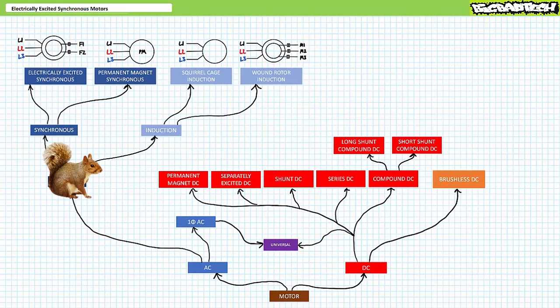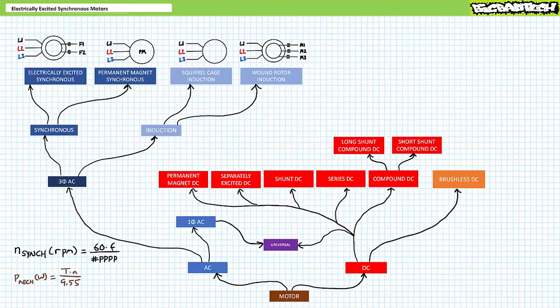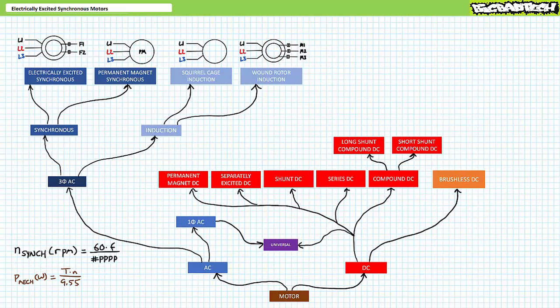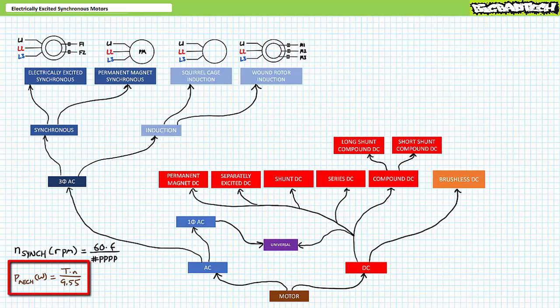Before we do so, let's pause at the split between three-phase AC induction motors and three-phase AC synchronous motors and discuss some commonalities for these two important styles of three-phase AC motors. Both synchronous and induction three-phase AC motors are characterized by a rotating magnetic field on the stator. The speed of the rotating stator magnetic field is known as the synchronous speed and is directly proportional to the excitation frequency and inversely proportional to the number of pole pairs per phase. Additionally, the direction of the rotating stator magnetic field can be reversed by interchanging any two stator leads inside a three-phase AC system. Lastly, one could determine rotating mechanical power in watts as a product of torque in newton meters times rotational speed in RPM divided by the constant 9.55. These properties remain true for all three-phase AC motors, synchronous and induction.